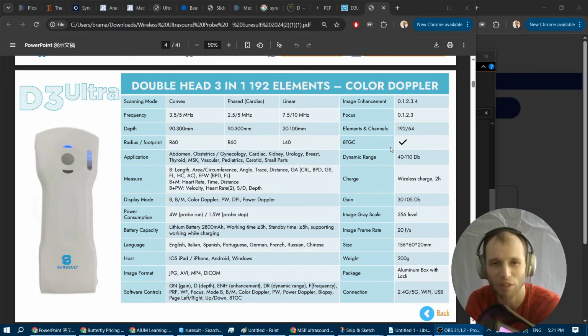Now, it does have presets, which gets you sort of close. I tend to put the gain up to max, but for dynamic range, for the set of focal points, you get 2 focal points on screen and you can press the button to move them around. For the depth setting, in fact, that's probably the biggest complaint about it, is there aren't enough depth settings. You basically have 4 depth settings and you can't go 1 centimeter at a time. It's something like 15 centimeters, 10 centimeters, 5 centimeters, 2 centimeters. So it often isn't exactly what you want.